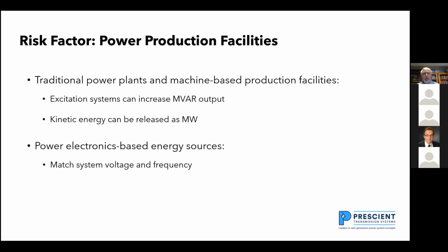The risk factors on power production facilities. Traditional plants are well understood. Machine-based production facilities are well understood. We have excitation systems that can increase the MVAR output, and we can release kinetic energy as megawatts. The power electronics based need additional modeling and additional study. A lot of the power electronics based are on homeowners' rooftops, and we have to make sure we've got all of those represented at each substation in a lumped model.